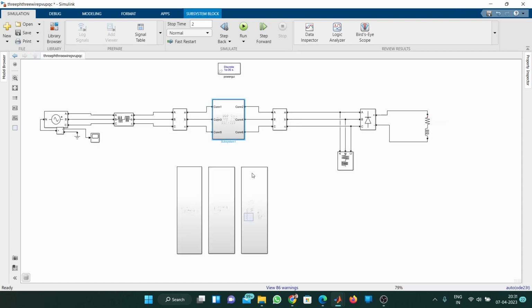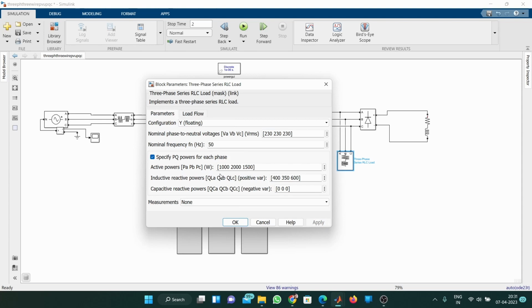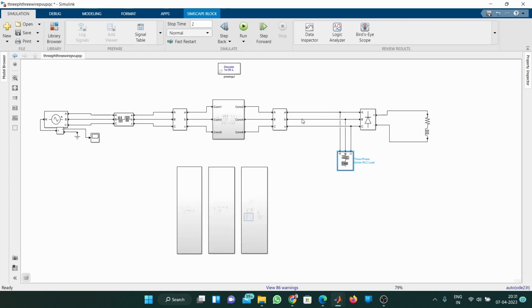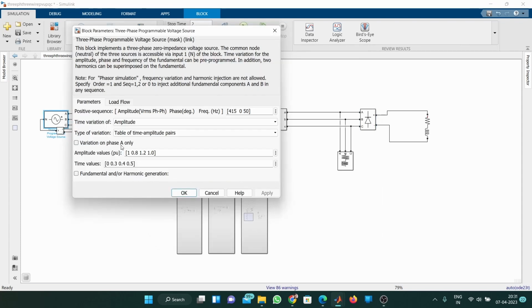So we are going to see the reduction in harmonics, and the unbalanced load current becoming balanced on the source side. Here we have taken the load as unbalanced, with different values given for the active and reactive power. So the current on the load side will remain unbalanced, and the current on the source side, which we have measured here, will be balanced. Here we have used a bridge rectifier to create harmonics in the system, which will be mitigated on the source side. Now for the DVR, we have given a change in the voltage amplitude.